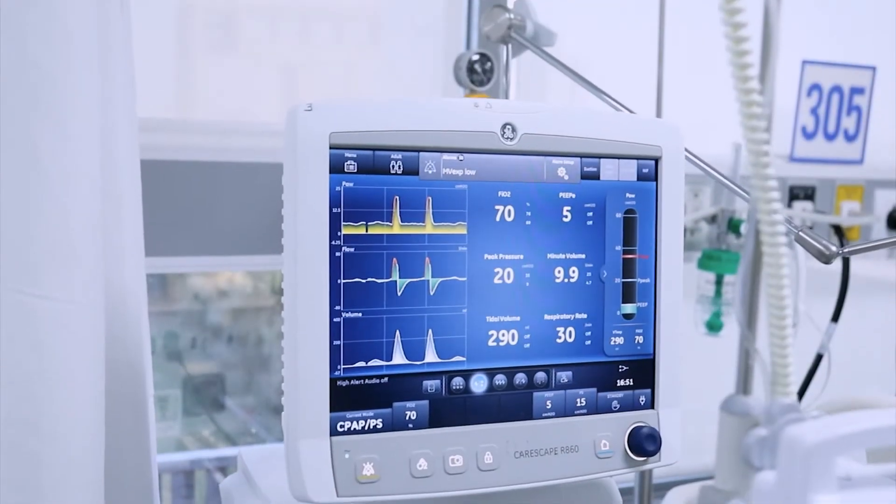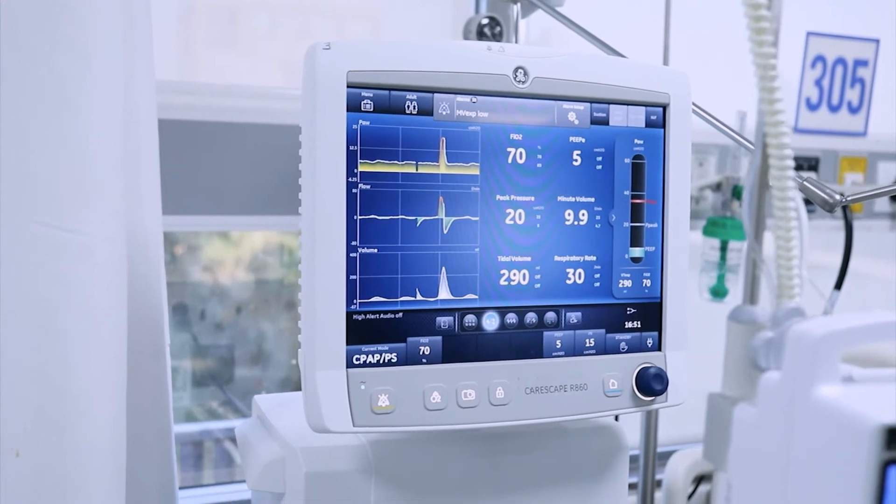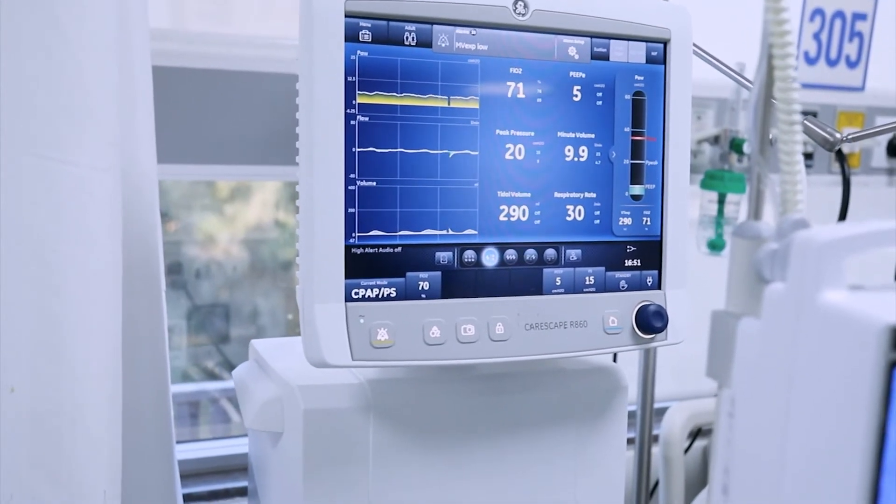FRC — that is Functional Residual Capacity — is a tool which quantifies the loss of volume, the quantification of the mass of lung which is lost because of acute injury. It works by nitrogen washout technology. Functional residual capacity is the amount of air that remains in the lung after the end of exhalation. It can be measured in spontaneously ventilating patients, but is very difficult to measure when the patient is intubated. So technology was developed to measure FRC using nitrogen washout.